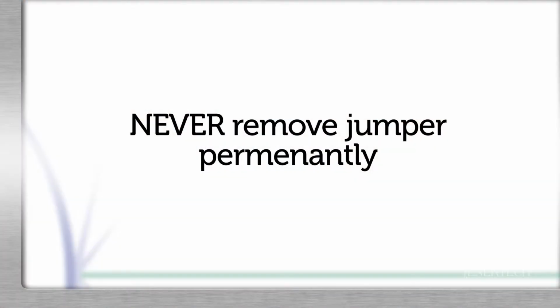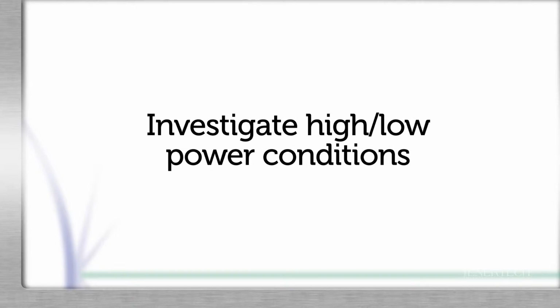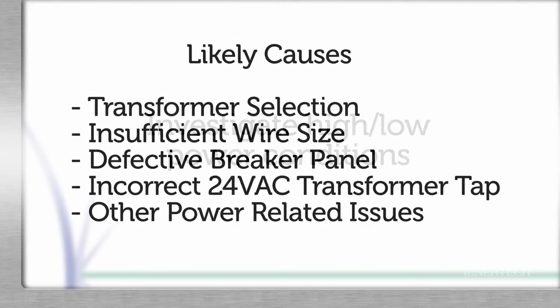An over-under voltage condition could cause premature component failure or damage to the unit controls. Any condition causing this fault must be thoroughly investigated before taking any action regarding the jumper removal. Likely causes of an over-under voltage condition include power company transformer selection, insufficient entrance wire sizing, defective breaker panel, incorrect 24-volt AC transformer tap inside the unit control box, or other power-related issues.